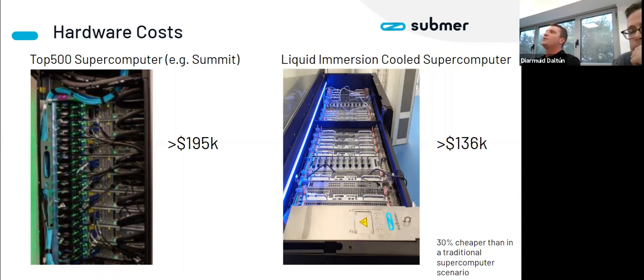Immersion opens up a whole new set of opportunities for not just server manufacturers, but even power supply manufacturers, where components need to be spaced at a specific distance based on ASHRAE standards, and with liquid environments those components can be placed much closer together. Submerging batteries and things like that is another opportunity, so UPSs submerged in immersion could deliver substantial benefits as well, and also ease the facility side, the design of the facility.